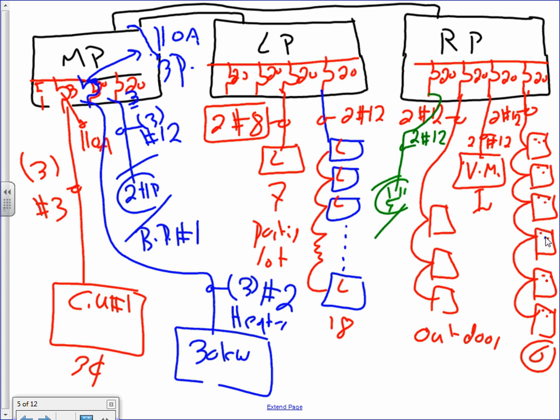This is for the receptacle panel. These are typical loads on the receptacle panel for this project. Can I have thumbs up over the receptacle panel? Switch to the lighting panel. For the lighting panel, here's what I suggest. And you're going to see why 18 fixtures. These are the number of fixtures you're going to feed, design-wise. You're going to see why I did the 18 in a second here. So you count 18 fixtures. You feed them from what? One 20 amp circuit with 2 conductors number 12. Can I have thumbs up, Chad? We're going to know why 18 in a second.